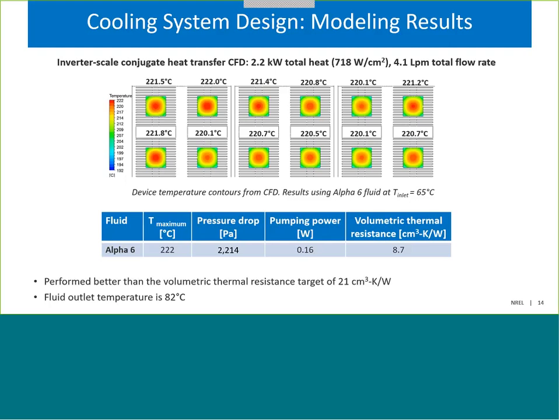This inverter scale model predicts a maximum junction temperature of 222 degrees C. And that's consistent with our prior device scale models, which predicted about 220 degrees. We are predicting a temperature variation between devices of about 2 degrees, and we attribute that to the variations in the fluid flow rate that I talked about on the prior slide.